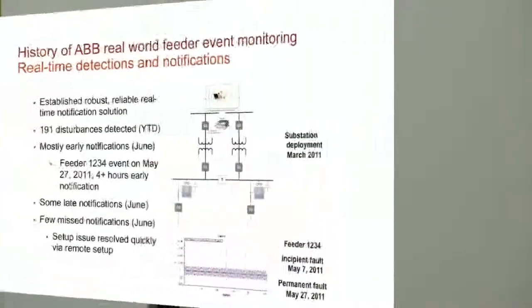Earlier, we did offline analysis - we were just building the algorithm, so they brought it back into the lab. They had the ComTrade files, developed algorithms, and played them back. That was the offline work. But here, this is taken to the next step - it's actually now installed and running real time, whether it's a load inrush, a recloser operation, or a fuse fault.